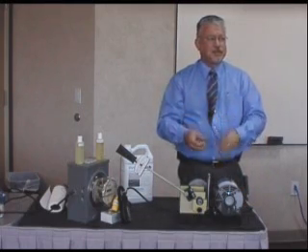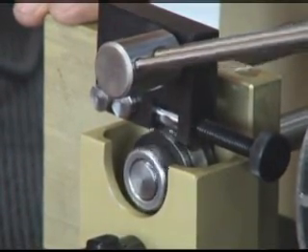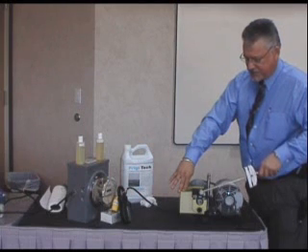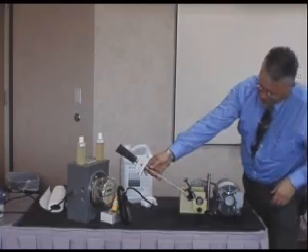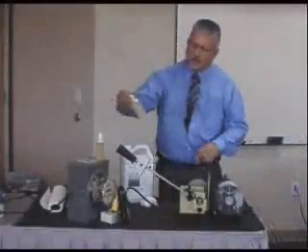I'm going to make another gouge about the same size so I can use it as a used-equipment baseline, and then I'll add Frigitec to see what difference it makes. Torque-wise it locks up at about 15 to 16 pounds — we even get a little bit of smoke coming off the bearing because of the heat it's generating. Now we have a gouge about the same size as before — pretty rough and pretty big.